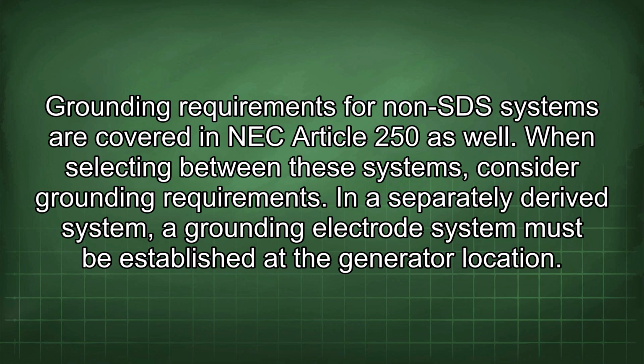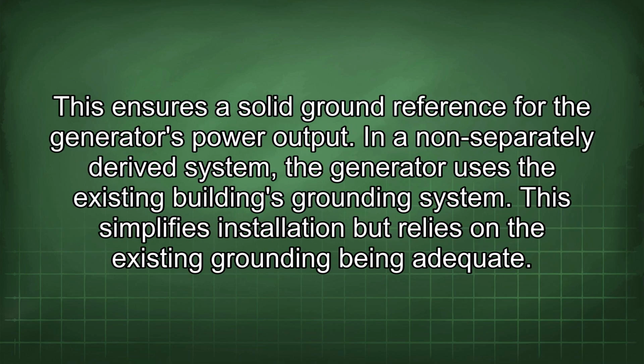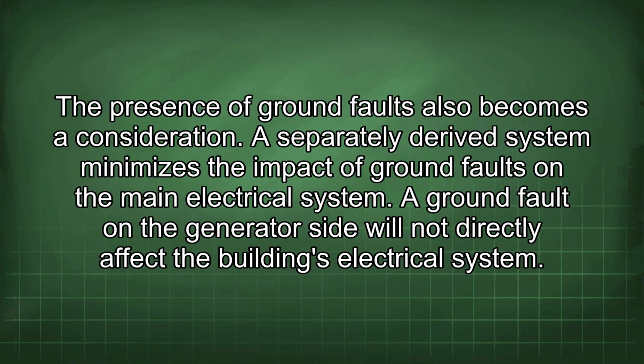When selecting between these systems, consider grounding requirements. In a separately derived system, a grounding electrode system must be established at the generator location. This ensures a solid ground reference for the generator's power output. In a non-separately derived system, the generator uses the existing building's grounding system. This simplifies installation but relies on the existing grounding being adequate. The presence of ground faults also becomes a consideration.